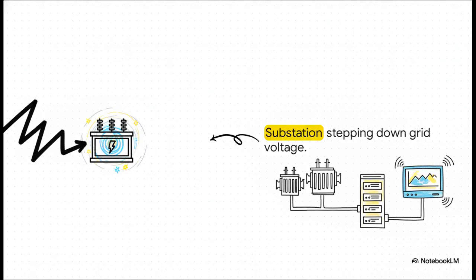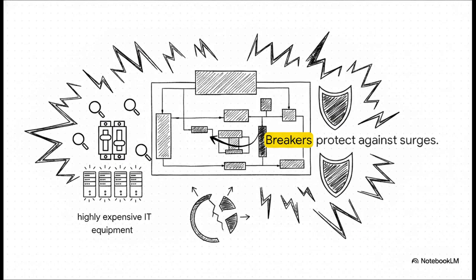You see, the immense raw power coming from the utility grid is far too intense to just plug a server rack into. Transformers step that incoming utility power down into a safe, usable facility voltage. The console pulls data from right here to ensure that step-down process is stable. Keeping up the pace, the power then flows through breakers and circuit protection. These are critical defensive checkpoints.